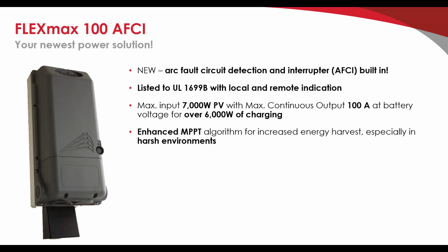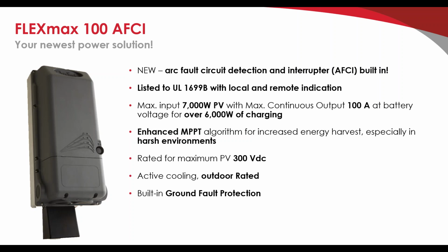The enhanced MPPT algorithm is new. Rated for 300 volts of PV, active cooling, outdoor rated, built-in ground fault protection, which was not new on this generation, but new compared to our other charge controllers. So you no longer need the old green GFDI breaker in the load center. You can use any standard breaker for the ground fault.